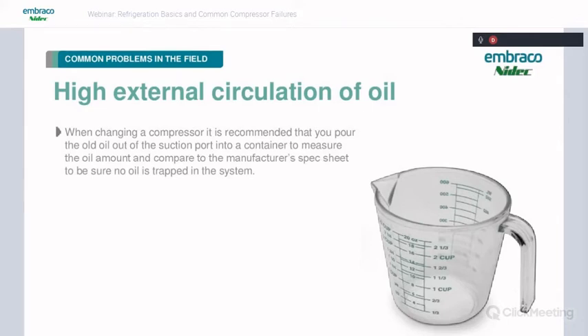But it is recommended to pour the oil into a container and measure it and make sure it's within plus or minus 2% of what's listed on the spec sheet. If we have less than that oil that came out of the compressor, it's recommended to go ahead and flush that system with some system flush. Make sure we get all that old oil out of there. Plus, the oil could be contaminated with acid and moisture, and it could also tear up the windings of the new compressors in very short order.